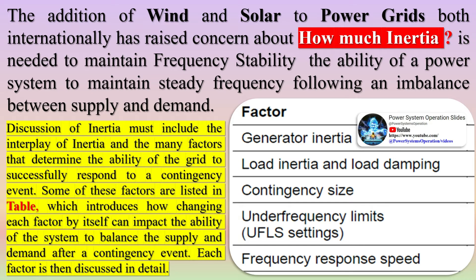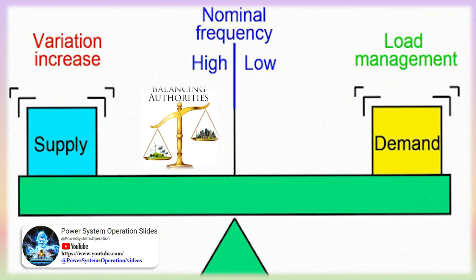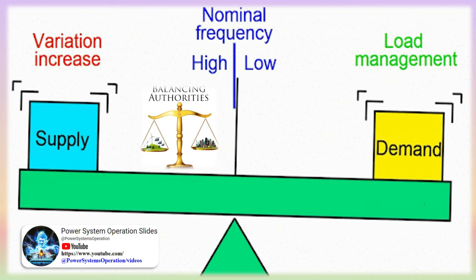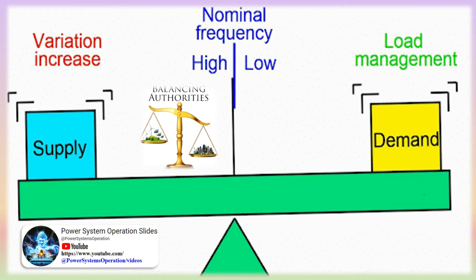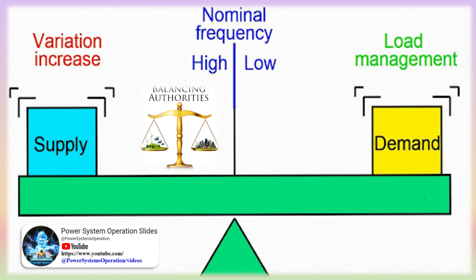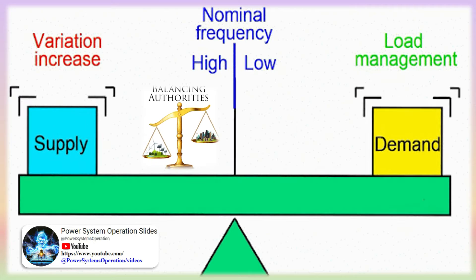All three types — rotor angle stability, voltage stability, and frequency stability — must be met at all times to maintain the security of the network. The addition of wind and solar to power grids has raised concern about how much inertia is needed to maintain frequency stability: the ability of a power system to maintain steady frequency following an imbalance between supply and demand. Discussion of inertia must include the interplay of inertia and the many factors that determine the ability of the grid to successfully respond to a contingency event.